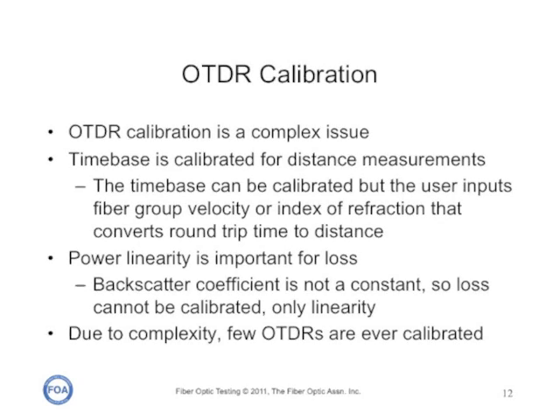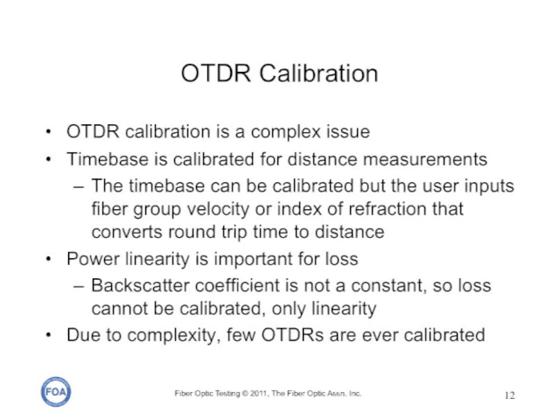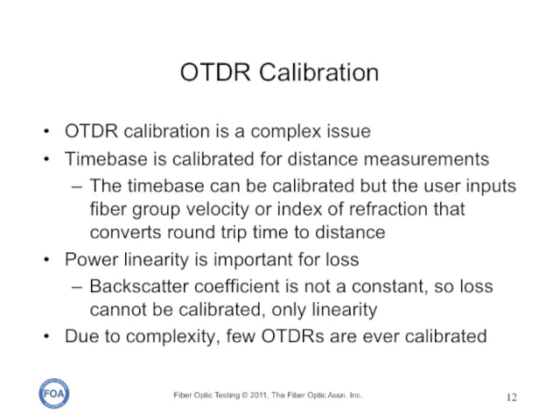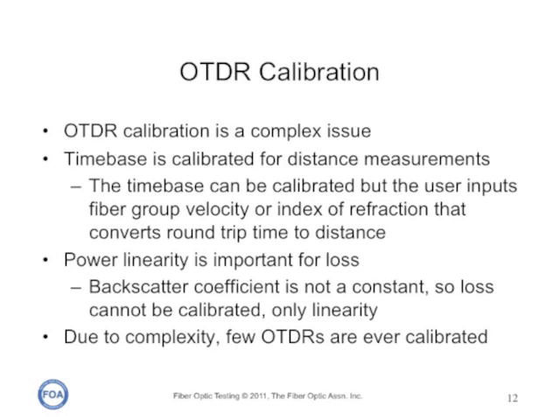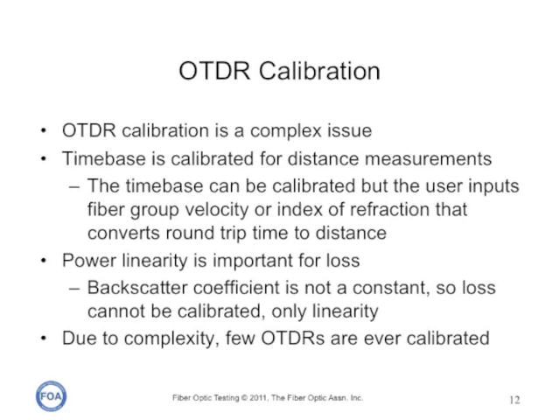We often get questions about OTDR calibration. OTDR calibration is a complex issue. The time base is calibrated for distance measurements, but the actual distance measurement is going to be influenced by the fiber NVP or index of refraction, so it's not a big issue. The power linearity is important for measuring loss, but the backscatter coefficient is not a constant, so loss cannot really be calibrated — only linearity. Due to the complexity of calibrating OTDRs, very few are ever calibrated, and we actually don't know any labs that do it routinely.